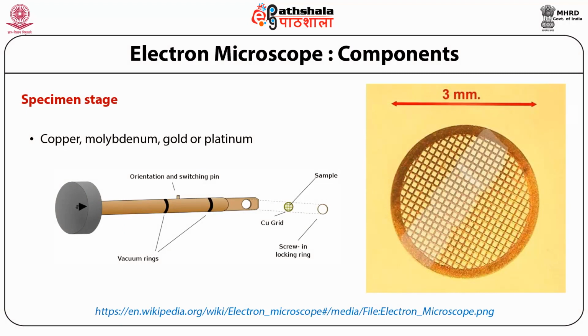Now this is made up of copper, molybdenum, gold or platinum, and as you can see in these two pictures, on the right hand side we see the grid in which the sample is kept. The sample has to be ultra thin, around 100 nanometers in width, so that it can be properly visualized and electrons can pass through it easily. A thicker sample will have a problem in terms of resolution because most of the electrons might get trapped inside the sample and would just provide a dark black image instead of a high resolution image.